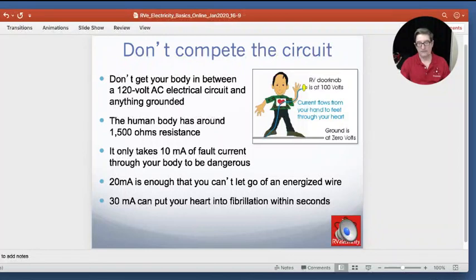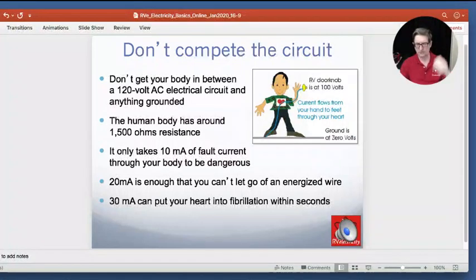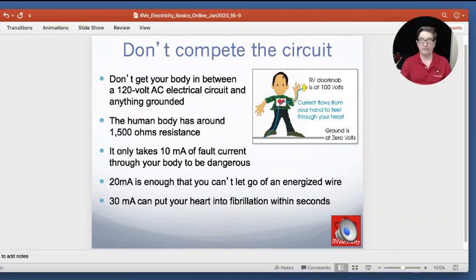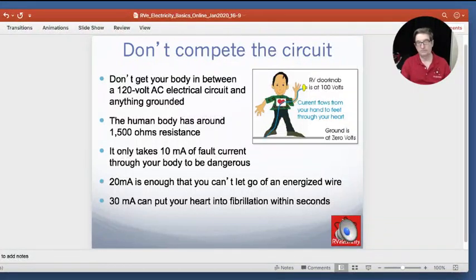One thing to be careful about is what the RV industry calls hot skin voltage — everybody else calls it contact voltage. If you're around high voltage power lines it's called step voltage. Basically it's this difference in voltage. You can see if this doorknob is around 100 volts and our poor little guy is standing on wet ground, he can become the current path. You do not want to get your body between a 120 volt AC circuit and anything grounded — it could be wet ground, another RV, a whole variety of things. Your human body has somewhere around 1,500 ohms resistance, which varies depending on the salinity of your sweat and how damp the ground or contact surface is.